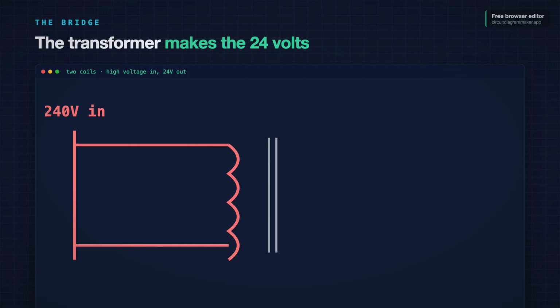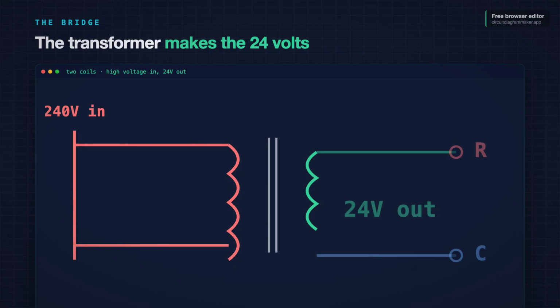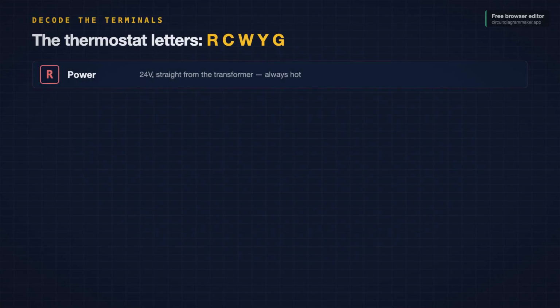The bridge between those two worlds is the transformer. It is a small block, often bolted inside the air handler or furnace. On the diagram, it is drawn as two coils side by side. High voltage goes into the primary side, and 24 volts comes out of the secondary side. That is it. The transformer is the little machine that makes the control voltage. Two wires leave that 24-volt secondary. One is labeled R. The other is labeled C. Hold on to those two letters because everything the thermostat does is measured against them.